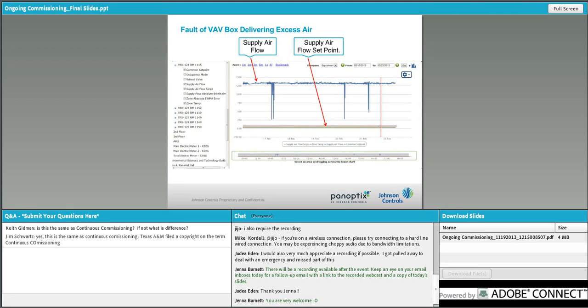This fault is for a VAV box, so the supply air set point on this is probably somewhere around 50 to 75, which is very low for a box of this size. Theoretically, this box should essentially be closed, but it's delivering over 1,250 CFM of air. So there's something wrong with this box. Again, detecting that there's a fault here is the easy part. Diagnosing exactly what's going on is the challenging part with FDD.